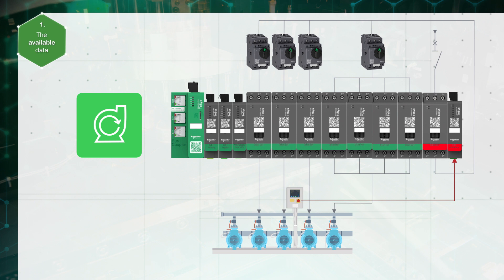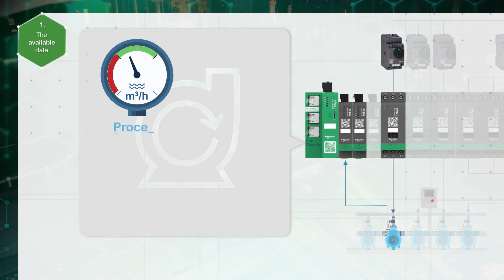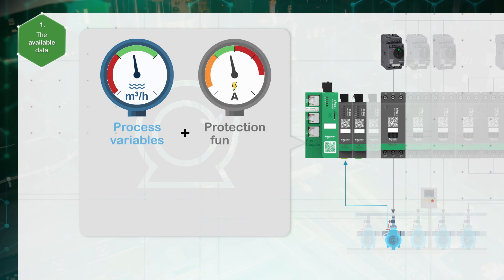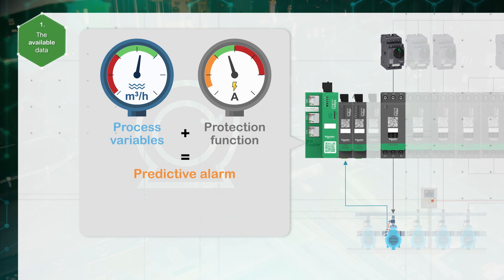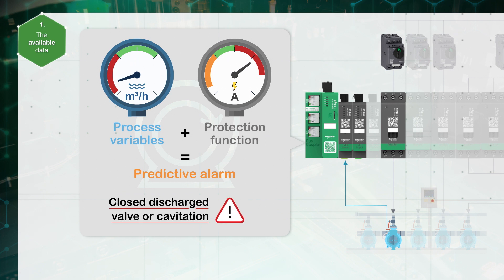Now let's focus on this application of pumping to see how process variables and predictive alarms can help avoid machine outage. For the pump avatar, we define the analog value from the flow meter as a process variable input. Combined with two protection functions, we define two predictive alarms: clogged inlet or closed valve in case of low flow and undercurrent; closed discharge valve or cavitation in case of low flow and overcurrent.